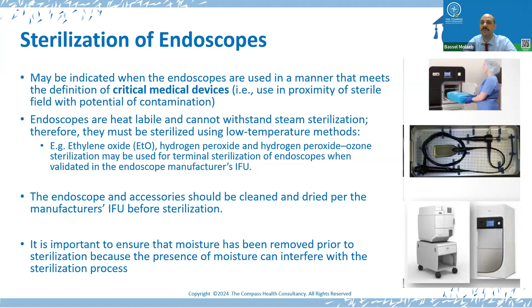Keep in mind that the endoscopes are heat sensitive and cannot withstand steam sterilization. Therefore, they must be sterilized using low temperature methods, for example, ethylene oxide or hydrogen peroxide or ozone sterilization as a means for terminal sterilization. And this should be validated as per the IFUs. The scope and its accessories should be cleaned and dried per manufacturer's IFUs before the sterilization. It is important to ensure that the moisture has been removed prior to sterilization, because presence of such moisture in the lumens may interfere with the sterilization process.